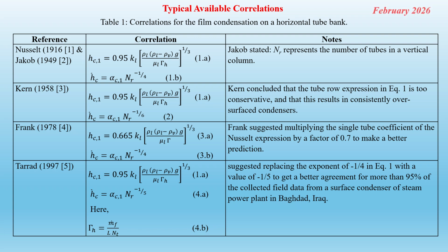So Jakob added a correction to the single tube condensation using equation 1b, where n sub r represents the number of tubes in a vertical column, to the power of minus quarter. Kern then presented an equation also based on the Nusselt equation, using n sub r to the power of minus 1 over 6, stating that Jakob's equation 1b is conservative and predicts a low heat transfer coefficient, which overestimates the required surface area of the condenser.